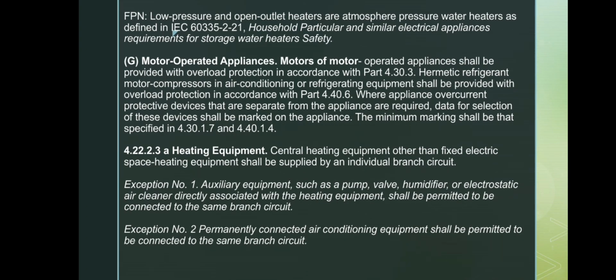Next is for motor operated appliances. Their motors must have overload protection following part 4.30.3. For hermetic refrigerant motors, compressors in air conditioning or refrigeration units, overload protection must follow part 4.40.6. If an appliance requires overcurrent protection that is installed separately from the appliance, the appliance must be marked with the proper data for selecting the protective device.